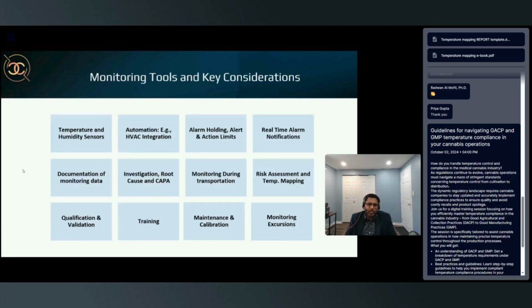I've done both paper and automated monitoring. With paper format, I do have data, but apart from telling me if it's out of specification, I have no use for it unless I'm trending it over multiple months and years, and I only have 2 or 3 data points per day. With automated monitoring, I have hundreds of data points I can use for trending, and even to identify persistent excursions.